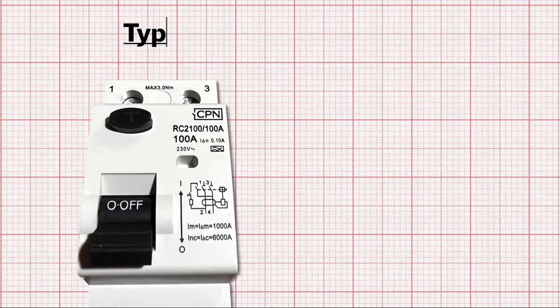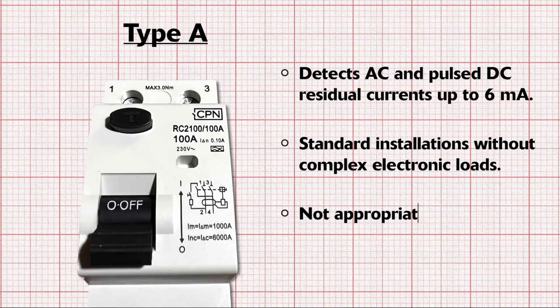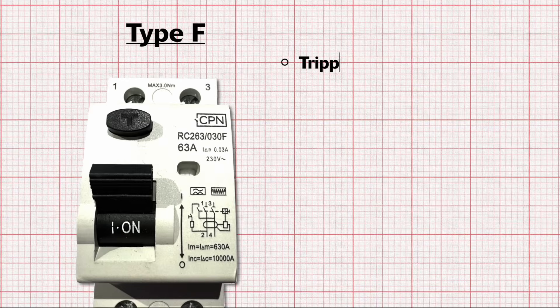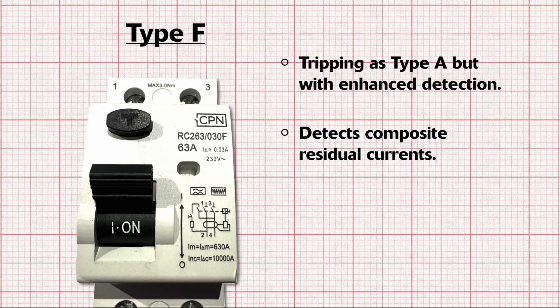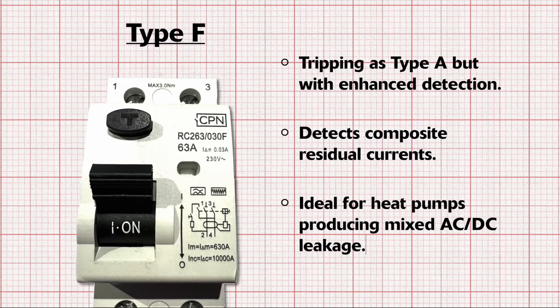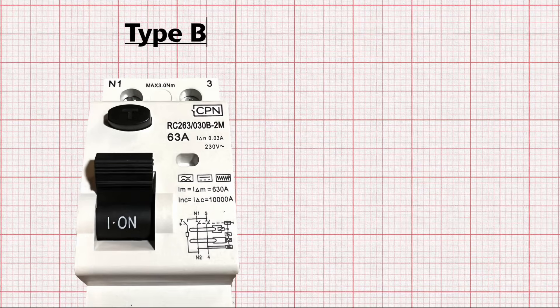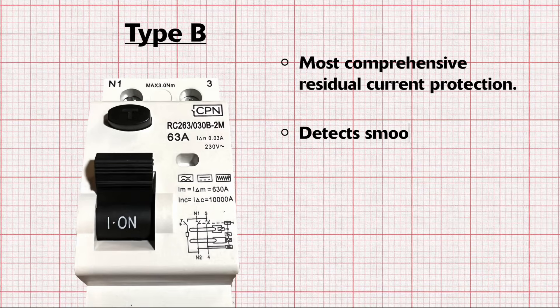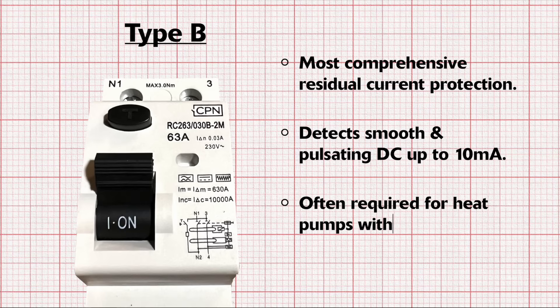There are several types of RCDs, each designed to handle different current characteristics. Type A RCD: this device is designed for alternating sinusoidal residual currents and residual pulsing DC up to 6 milliamps. However, it's not suitable for systems like heat pumps that have inverters that produce composite residual currents. Type F RCD: this type has the same tripping characteristics as type A, but can also detect composite residual currents, even those with slowly rising or suddenly applied components — suitable for heat pumps that generate mixed AC and DC currents. Type B RCD: offering the broadest protection, type B RCDs can handle residual pulsating DC currents superimposed on smooth DC up to 10 milliamps, and are often required for heat pump installations with specific inverters.